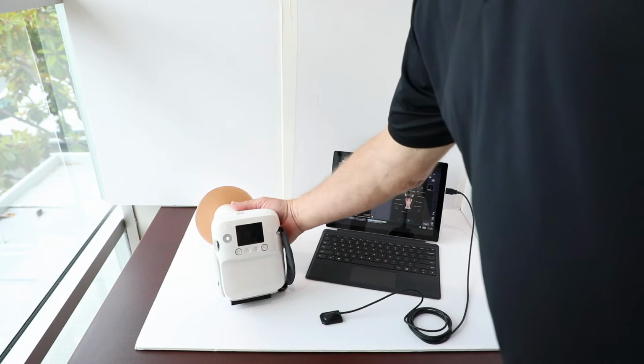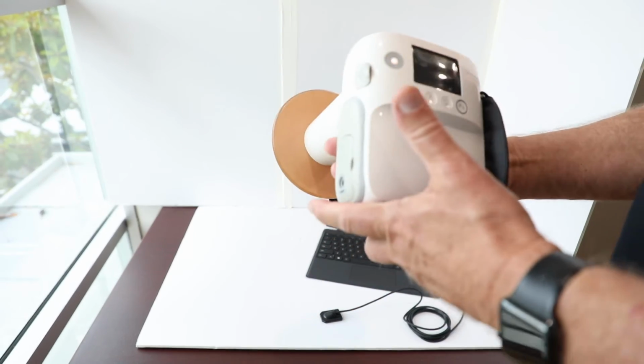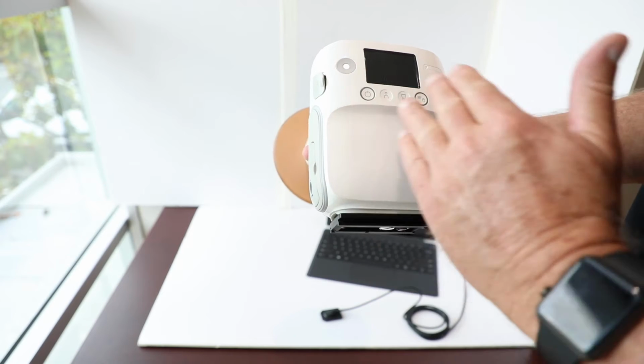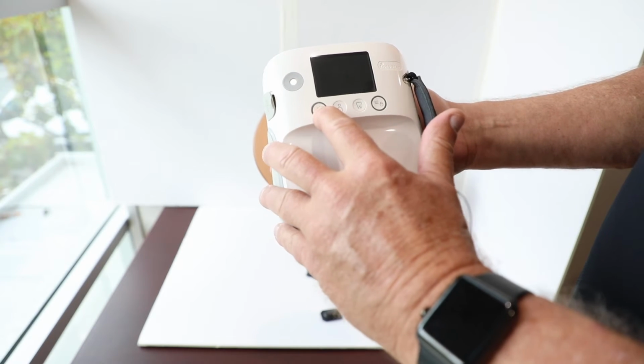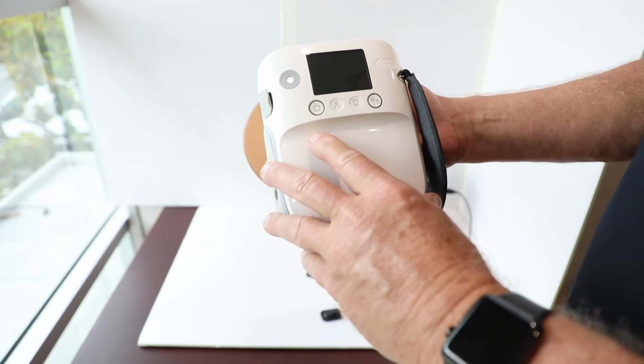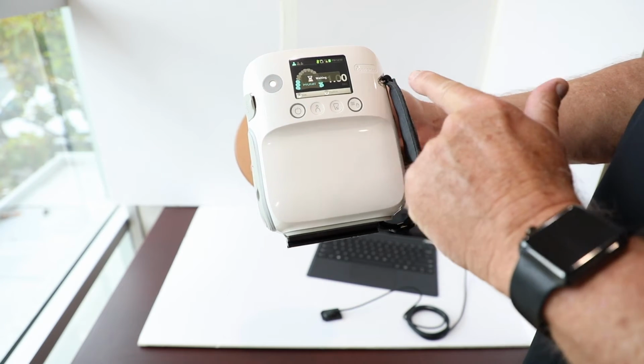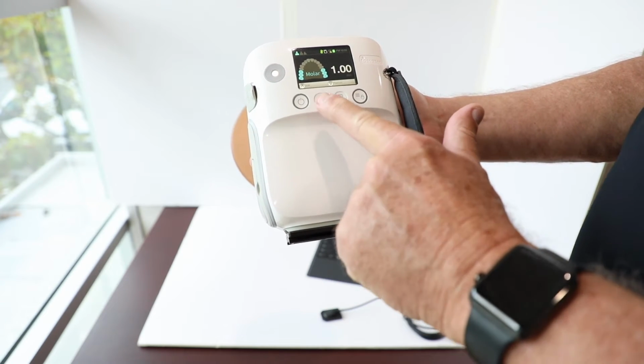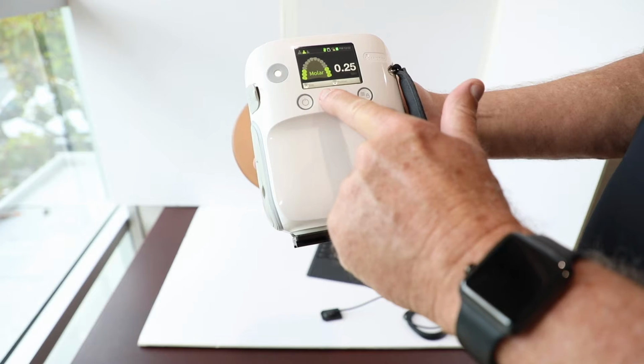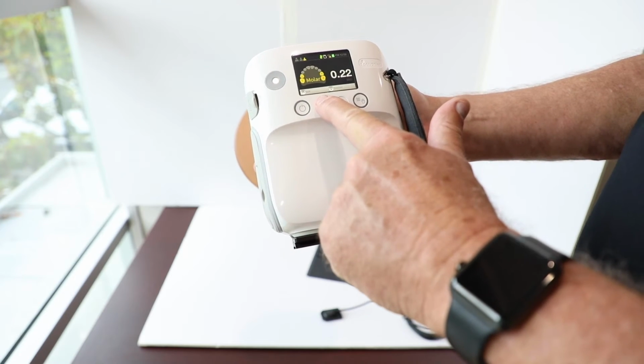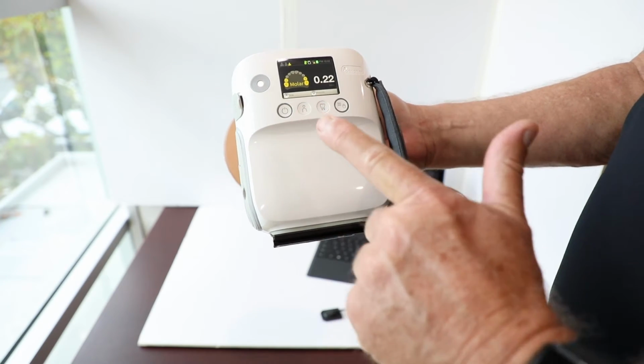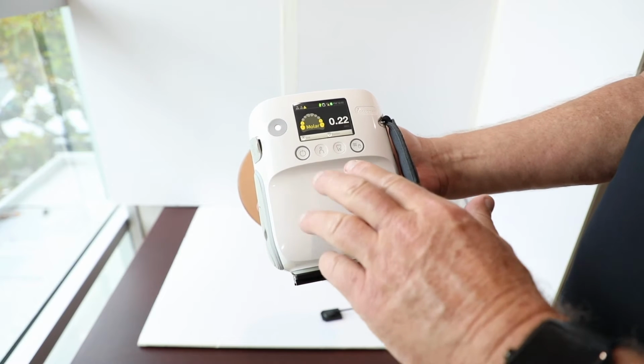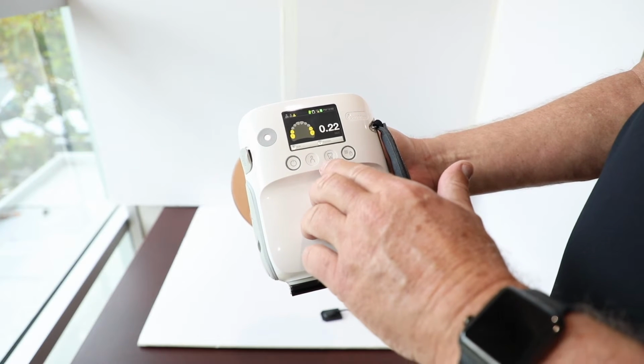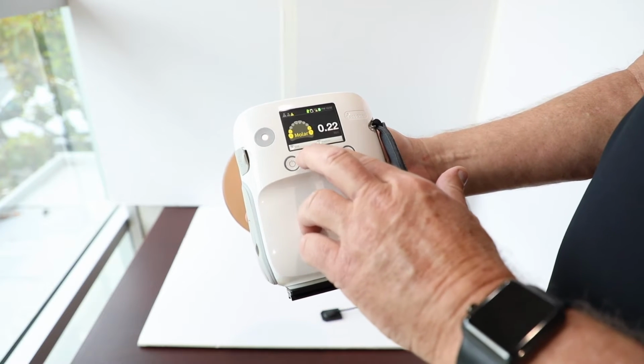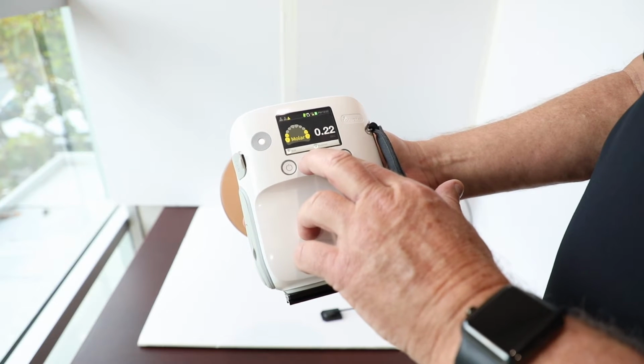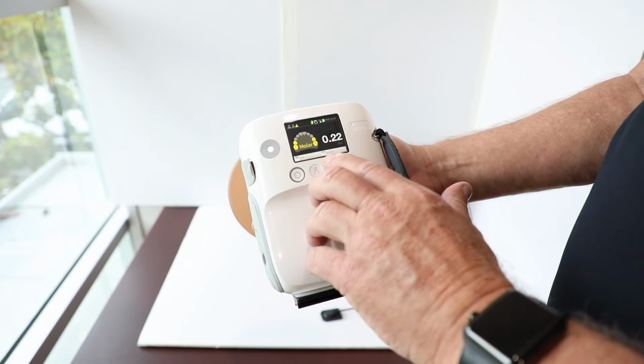Today I'd like to discuss the new handheld portable x-ray. You have the power button up here on the back. When you press that on, it comes on, you see the blue light flashing. You have the different size of patient. So basically the patient size, where it's a small, medium, or large patient. And then you can actually select the position of the teeth that you want to x-ray.